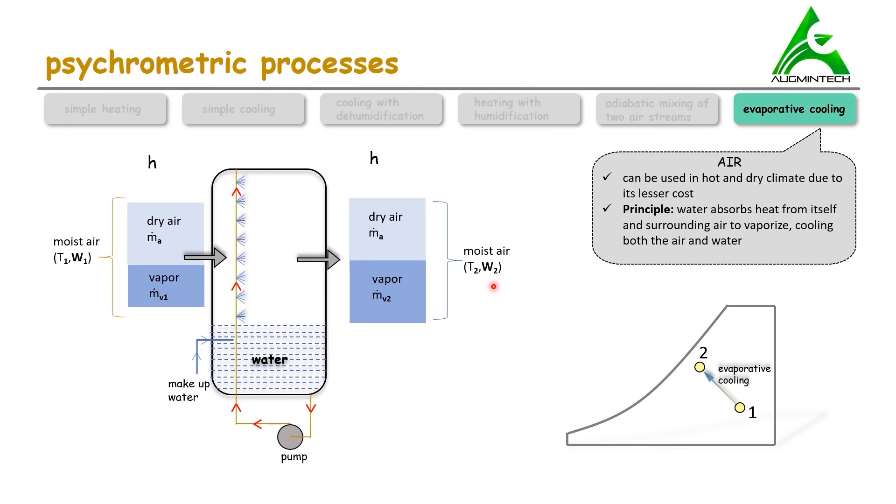Note that in this entire process, the enthalpy remains the same because there is no heating or cooling from any cooling or heating coil. Also, the wet bulb temperature remains the same. So this is the process of evaporative cooling.